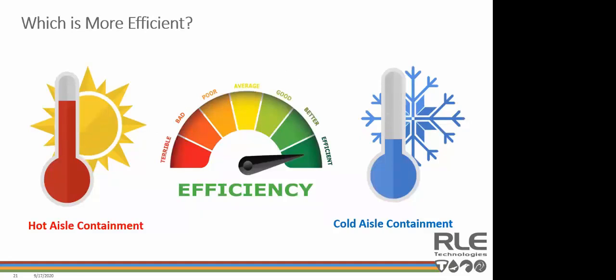So which is more efficient? This question gets asked a lot, and while it may differ based on data center size, layout, and capacity, generally speaking, hot aisle containment tends to be a better option. This is due to the fact that all the warm air is directed back to the CRAC units in the most efficient way possible, which increases the return air temperature and return efficiency of the CRAC units. However, implementation can be much more difficult, as stated before. If the data center wasn't purpose-built for hot aisle containment, retrofitting an existing space with a return air plenum in the ceiling is more expensive, and the extra efficiency gain over cold aisle containment may not be worth it. But again, this varies data center to data center.